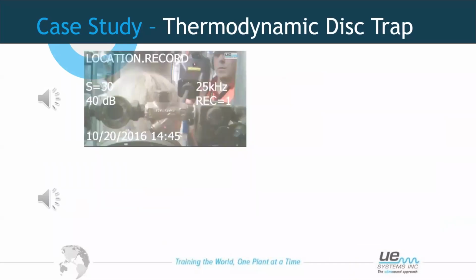So, a short case study. Okay, there's a short case study here from a training that I did some time ago where we looked at a few traps. And in this case study, this is a thermodynamic disc trap. Now, what we would expect to hear when listening to a thermodynamic disc trap would be opening and closing, so an increase and then decrease of turbulence every 2 to 10 times per minute. So that would then indicate to us a good trap.